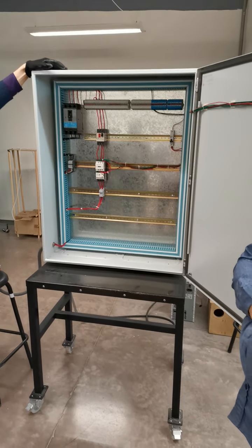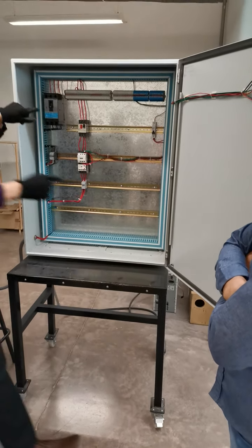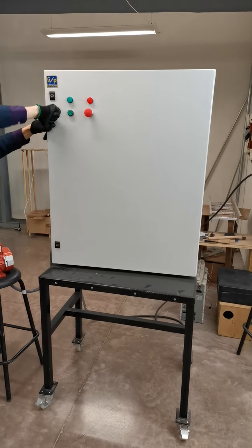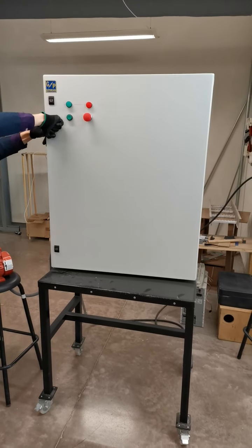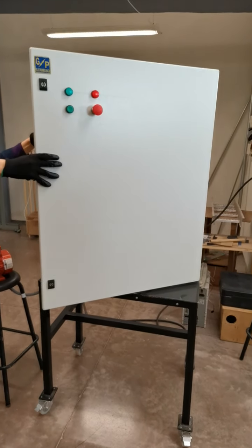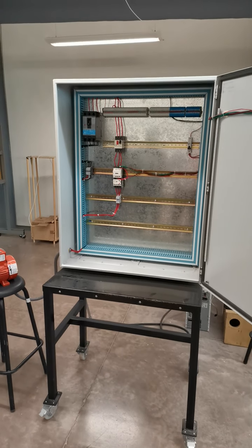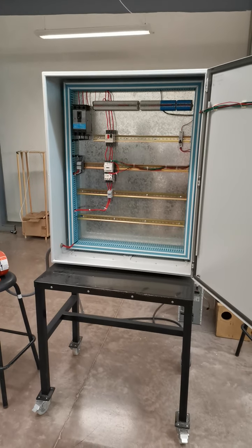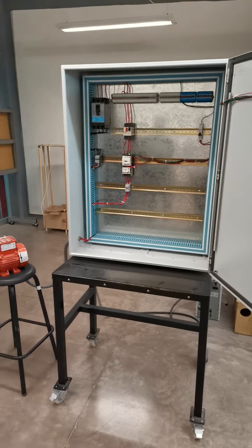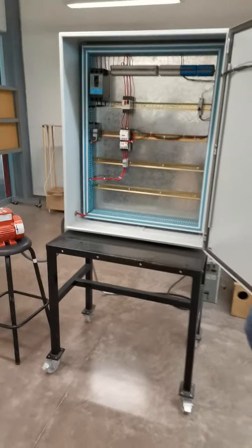But I guess you can relate that over there in the industry, this one is with a switch over here. So you need to deactivate the switch, you need to deactivate the main power in order to open it. If you do not deactivate it, you cannot open it. You have seen that one over there in the cabinet from the CNC. In order to open the cabinet, you need to deactivate the switch. It's not possible to activate the switch if the door is open.